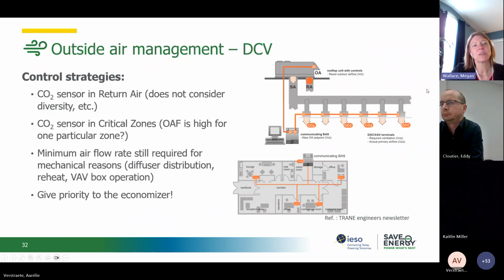Next slide. Some of the control strategies we can look at for demand control ventilation: we can put a CO2 sensor in the return air duct. That doesn't consider diversity in the system, though. You may have a meeting room full of people, and we wouldn't know that that room has a higher outdoor air requirement, because you're only measuring the mixed air in the return air duct. So you can put CO2 sensors in these critical zones to identify if they have a greater need for outdoor air.